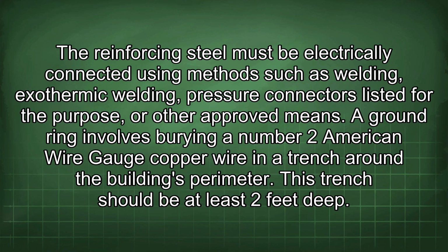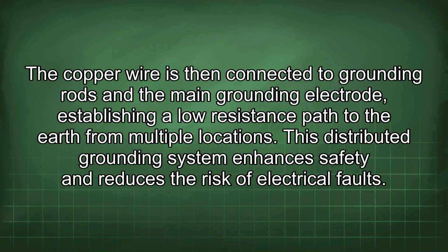or other approved means. A ground ring involves burying a number 2 American wire gauge copper wire in a trench around the building's perimeter. This trench should be at least 2 feet deep. The copper wire is then connected to grounding rods and the main grounding electrode, establishing a low resistance path to the earth from multiple locations. This distributed grounding system enhances safety and reduces the risk of electrical faults.